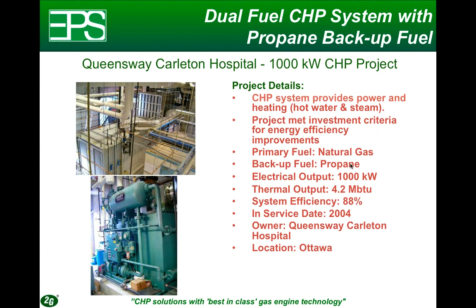Also unique here is that the system runs not only on natural gas but also has propane as a backup fuel. The hospital already had propane as backup fuel for their boilers and asked if they could use that same propane as backup for the cogeneration system. So in the worst-case scenario, with both a natural gas interruption and a power outage, the hospital can still run this unit on propane and deliver power and heat.